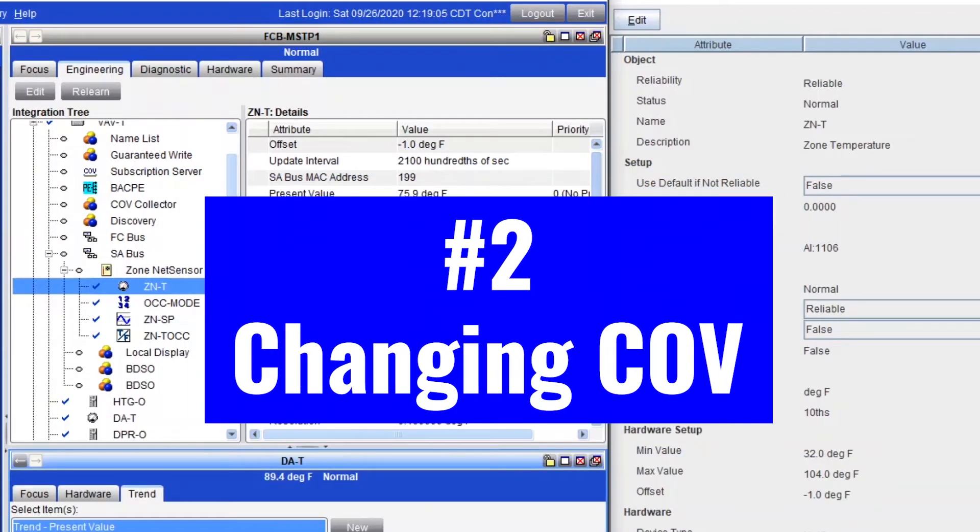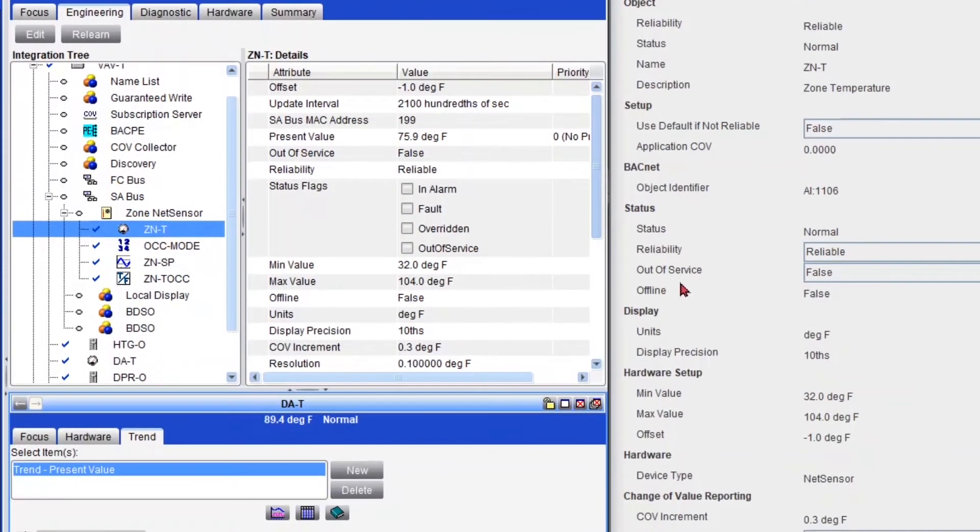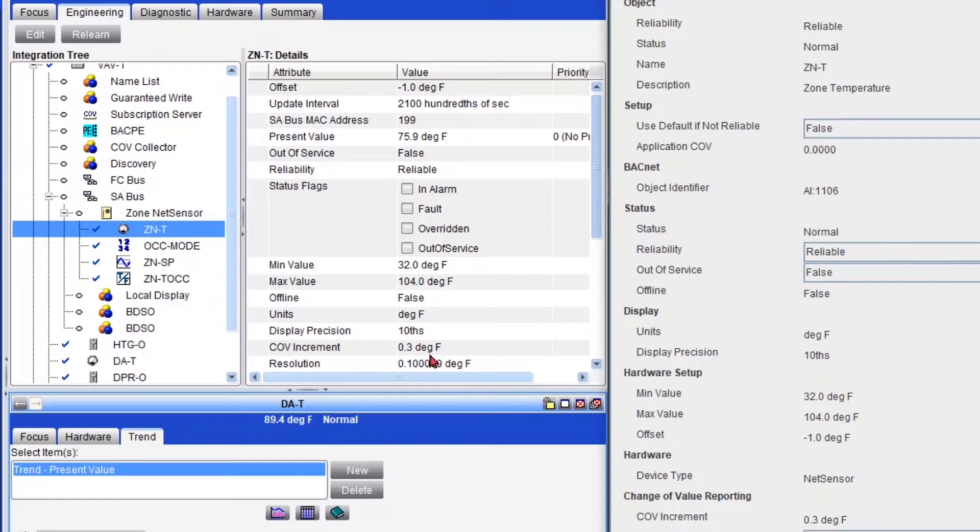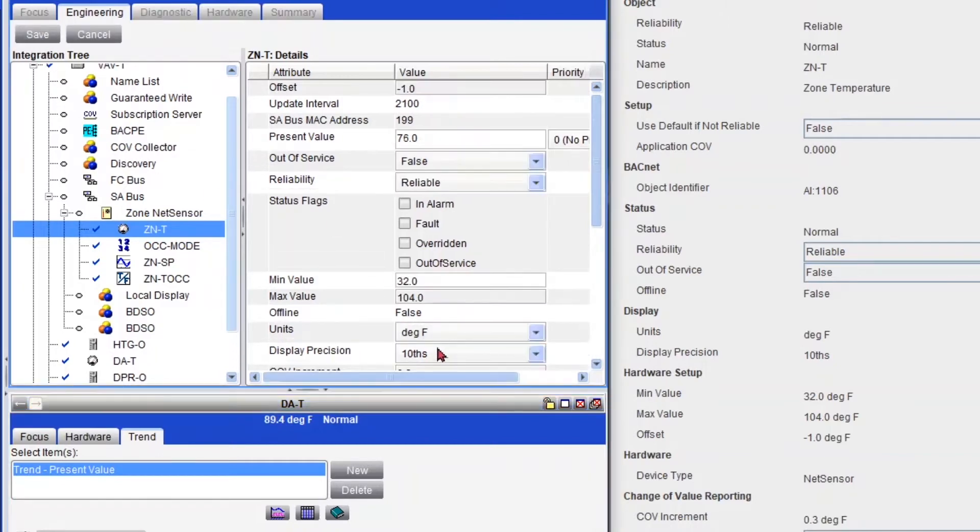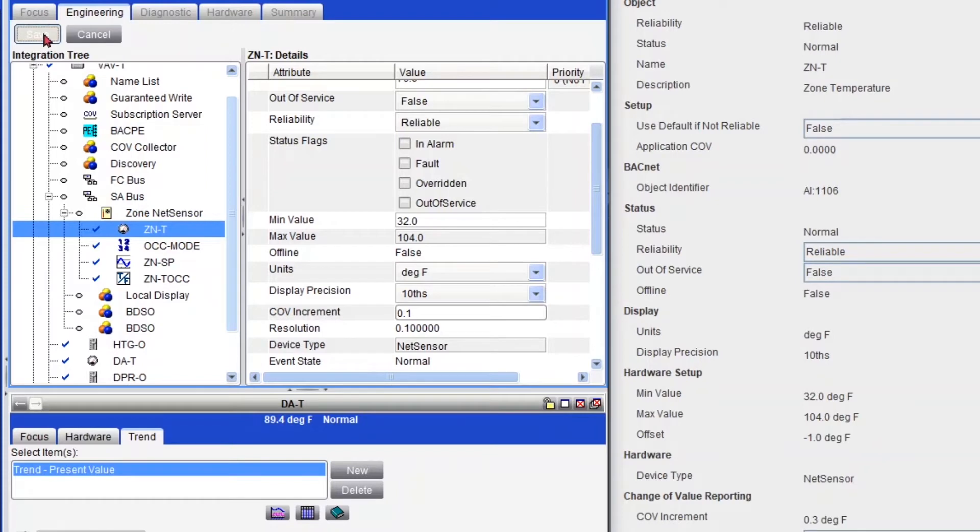So for my second trick, changing the COV increments or change of value, which you can find it right here in CCT, in my zone temperature, or over here in Metasys, I like to have it at least set to 0.1. And I'll explain why with an example. So let's first change this to 0.1 and then save.